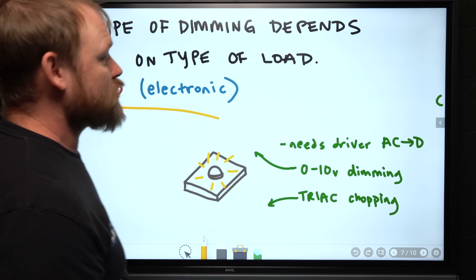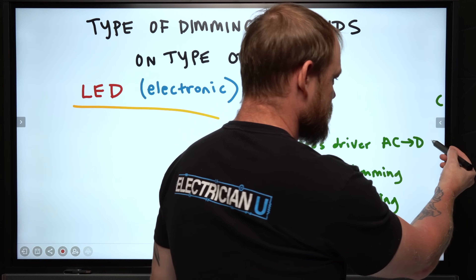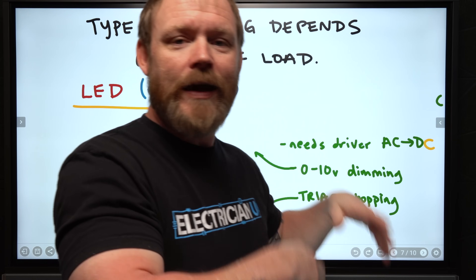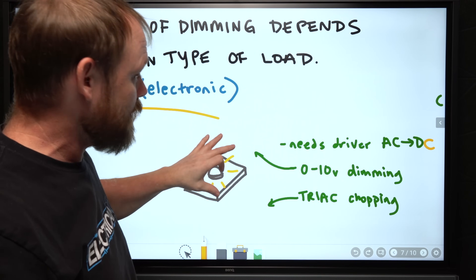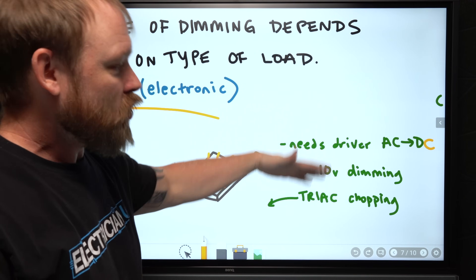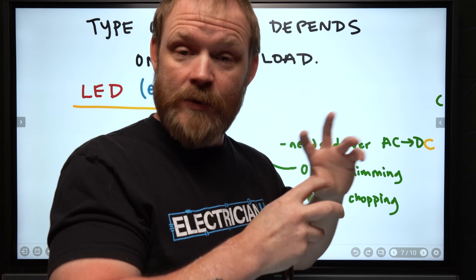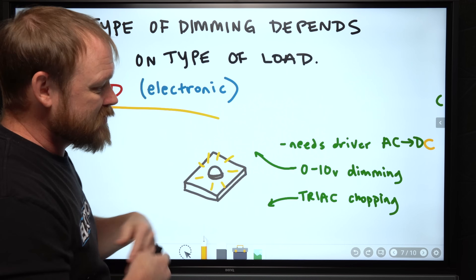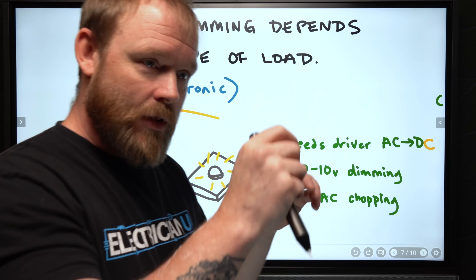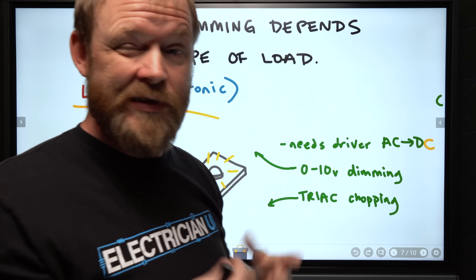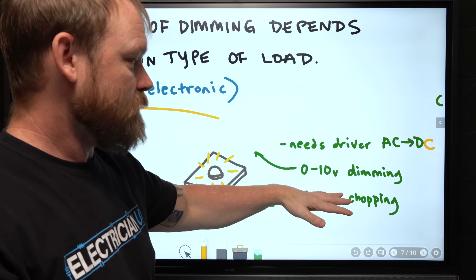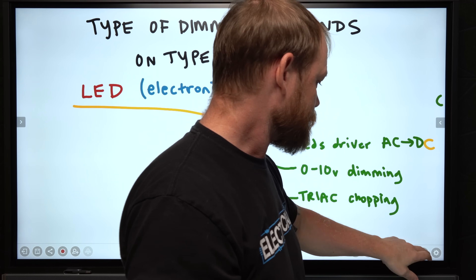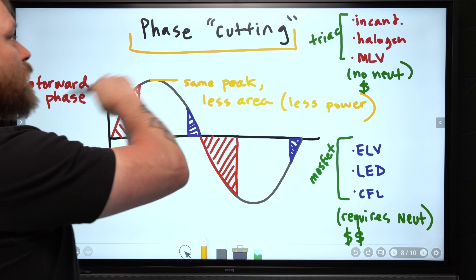LED lighting is very common and electronic in nature - it needs a driver. You're taking AC and converting it to DC, and DC drives the actual bulb. LEDs can use zero-to-10-volt dimming for external control of dimming levels, or they can still use a triac. A lot of normal wall dimmers used in houses chop part of the waveform off - that's how they achieve their dimming.